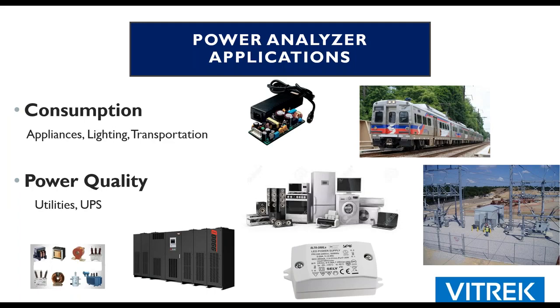So you hook up your power analyzer, and now you've got your product running, and you're just making sure that it's actually meeting all the specifications, mainly for efficiency, making sure the unit is operating as it's supposed to. In this case, you're monitoring the voltage, the current, the watt hours, how much power this thing is really using over a specified period of time.